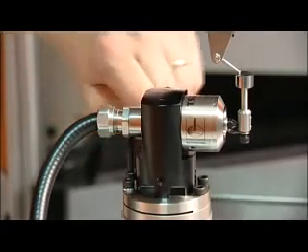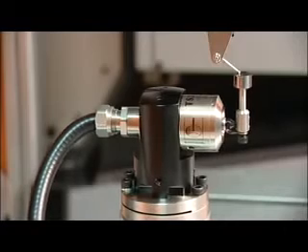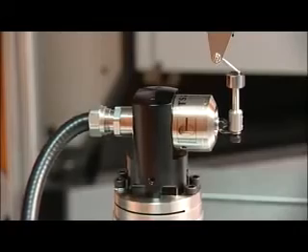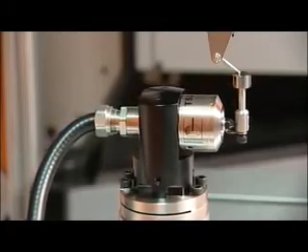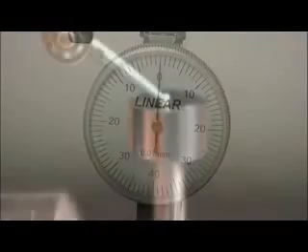For example, to lower the front edge of the stylus, rotate the bottom bolt anti-clockwise and the top bolt clockwise. This should be adjusted so that less than 5 microns of error is seen across the surface.